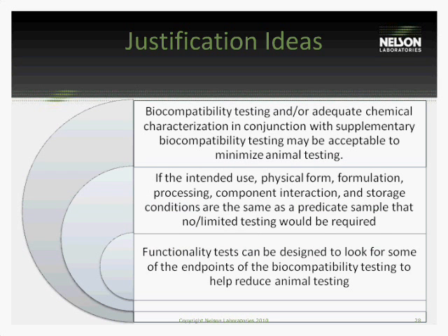There are some other specifics also with implantation and chronic toxicity that we can also look at. What we need to do here, though, is you need to have a good conversation with a biocompatibility person before you start those functionality tests, so that we can actually incorporate those endpoints into the functionality protocol to be able to help justify out of the testing at the back end.